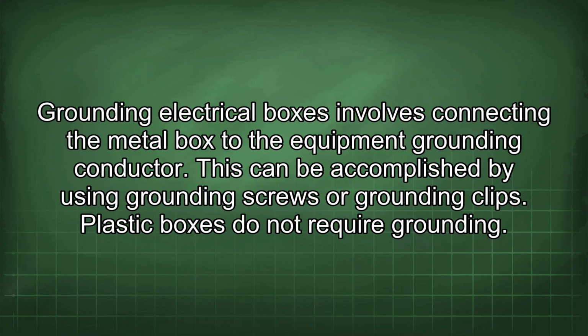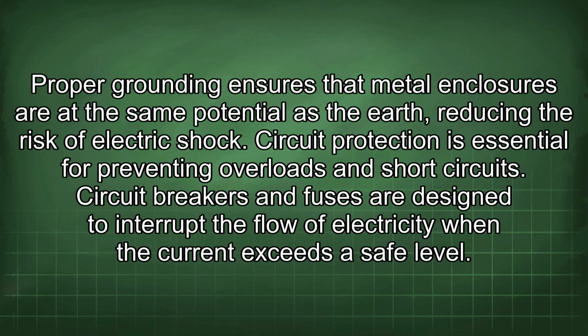Grounding electrical boxes involves connecting the metal box to the equipment grounding conductor. This can be accomplished by using grounding screws or grounding clips. Plastic boxes do not require grounding. Proper grounding ensures that metal enclosures are at the same potential as the earth, reducing the risk of electric shock. Circuit protection is essential for preventing overloads and short circuits. Circuit breakers and fuses are designed to interrupt the flow of electricity when the current exceeds a safe level.